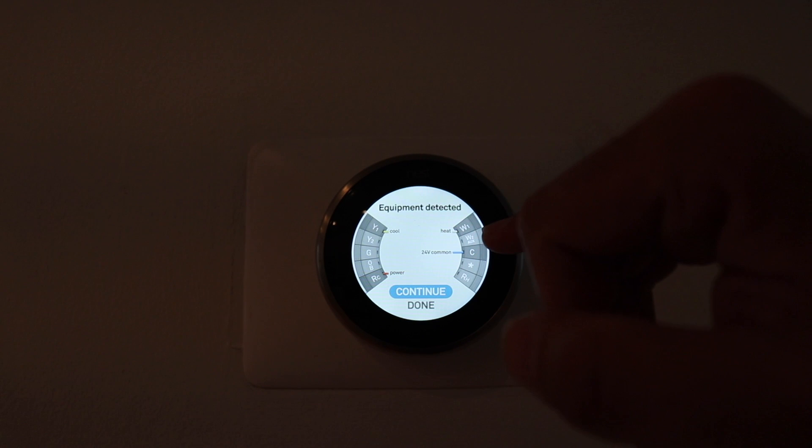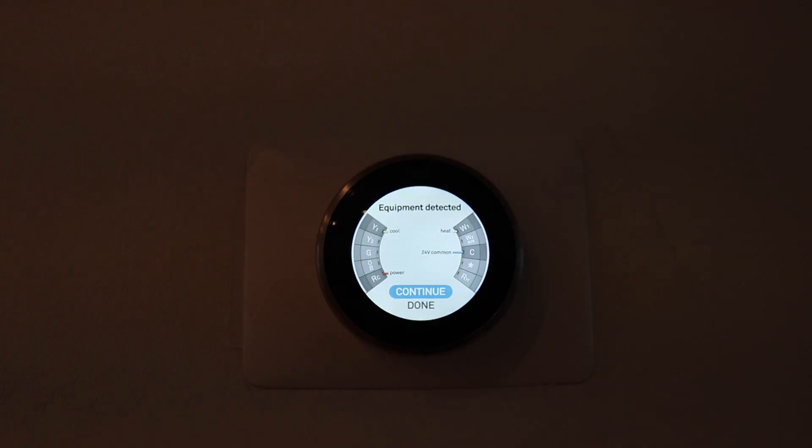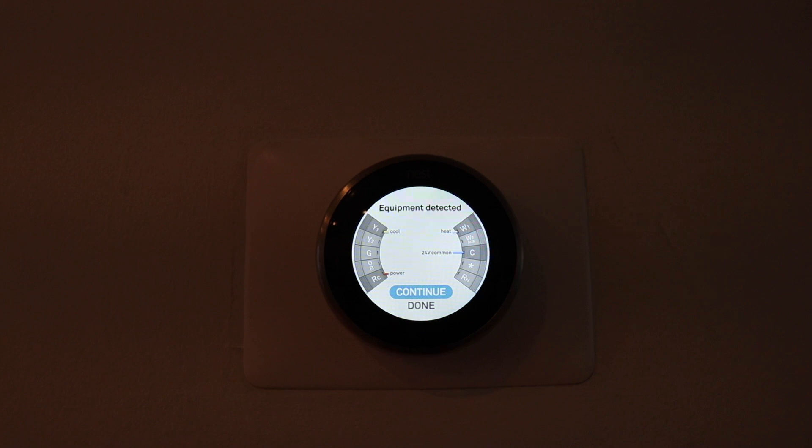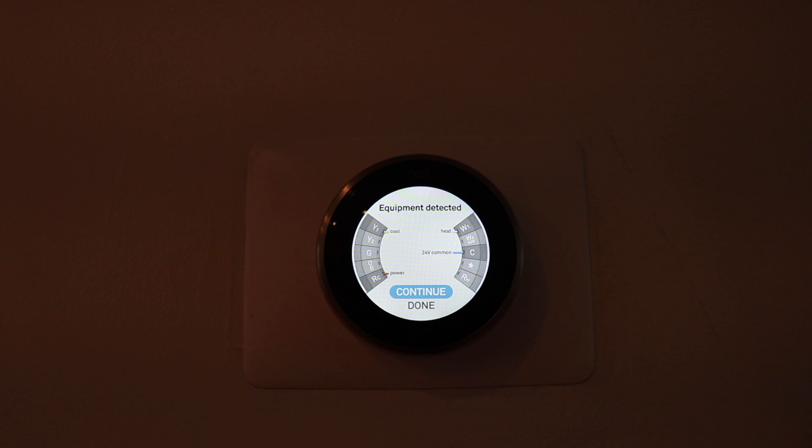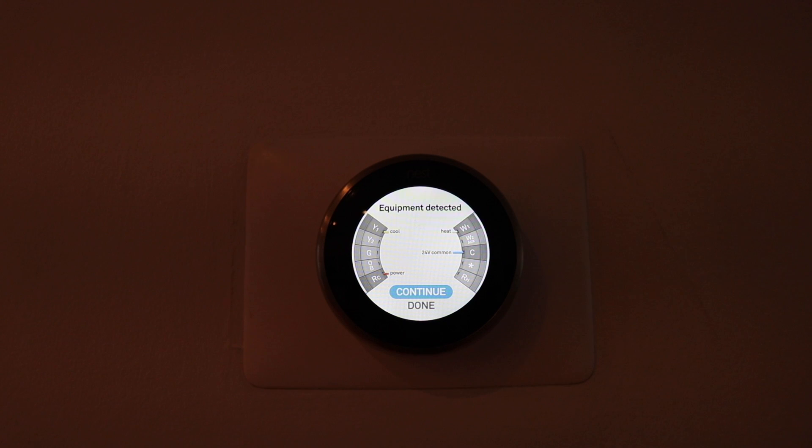It's going to show you that you've got your cooling, your heating, your heating, your common wire, and your power connected. If you were having common wire problems, this should solve your issue. And it is one of the ways that you can add a common wire to your Nest thermostat.